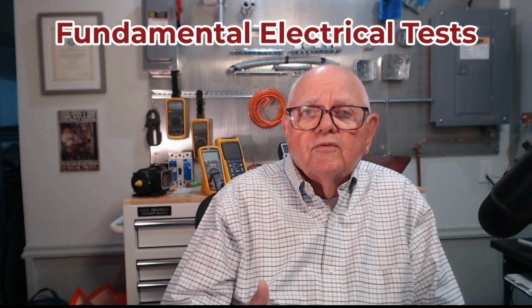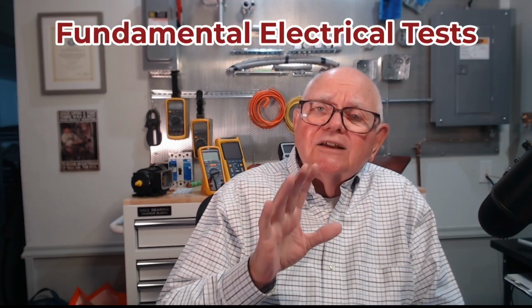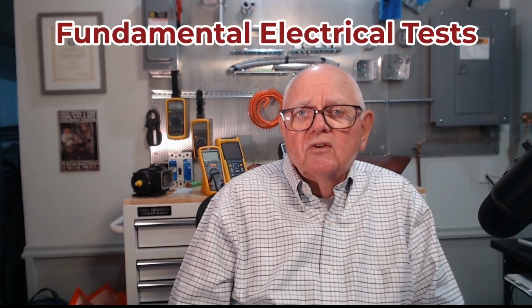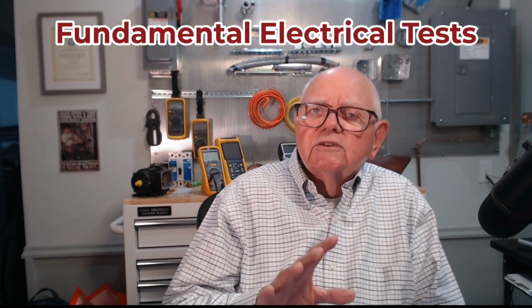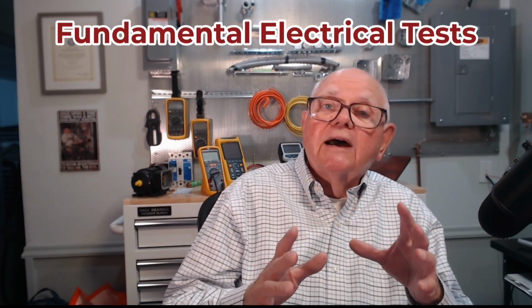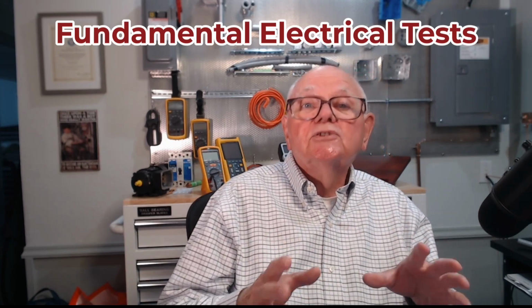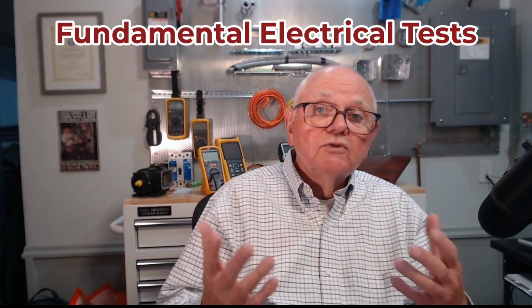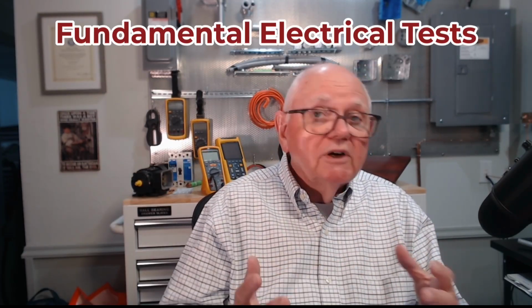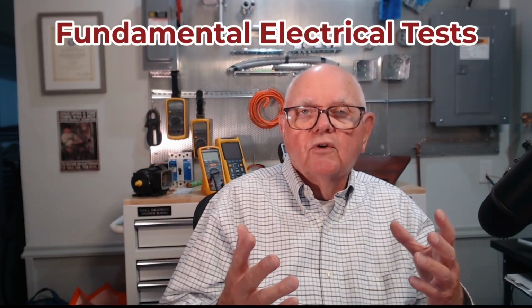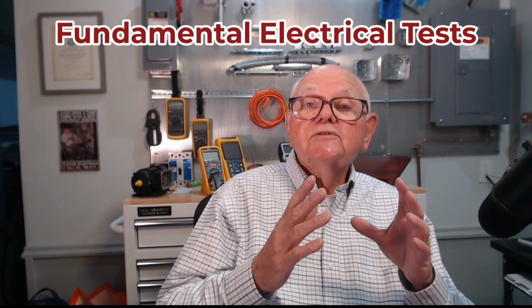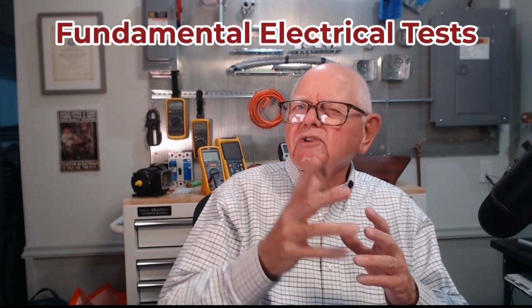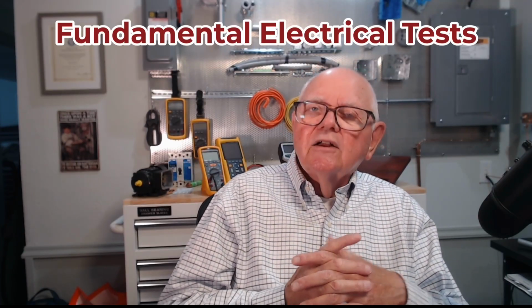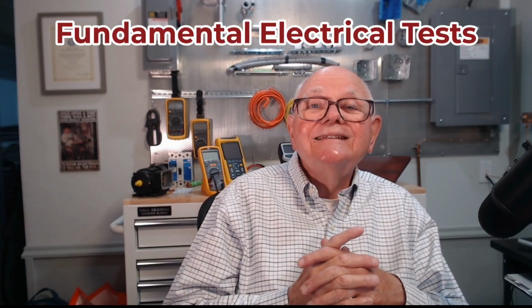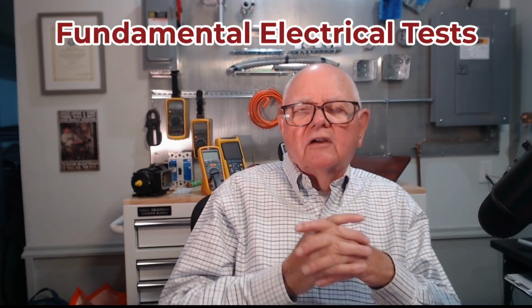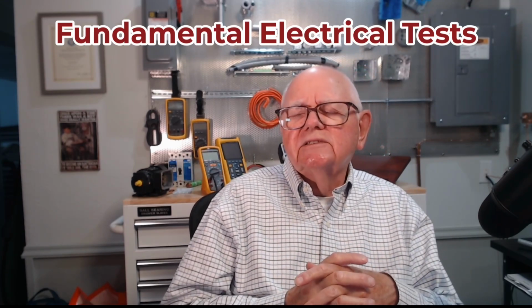Now, once you determine what that electrical equipment is and how often to perform maintenance on it, the question is what maintenance to perform. Once again, there are certain basic electrical areas or testing that you have to take a look at and perform. So that's what we're going to talk about. The first topic we'll talk about is bolted connections and terminations. As I said, if they're too loose or over-tightened, it can produce too much heat, cause overheating problems and so forth, and that's an issue for us. So we're going to learn how to test and inspect our bolted connections. Also covered in the NEC, 110.14(D). But we're going to talk about the maintenance issues today in 70B.